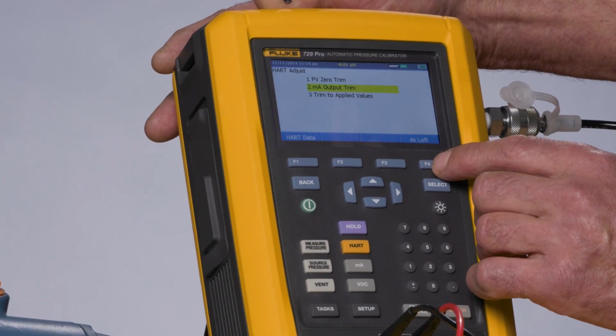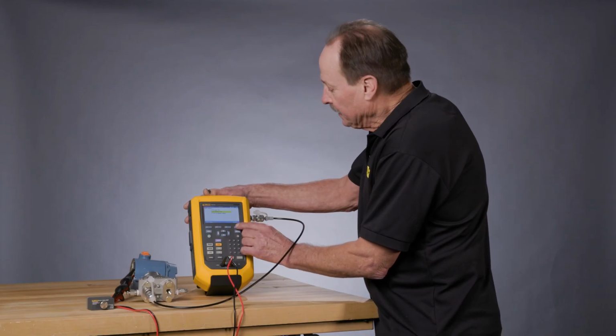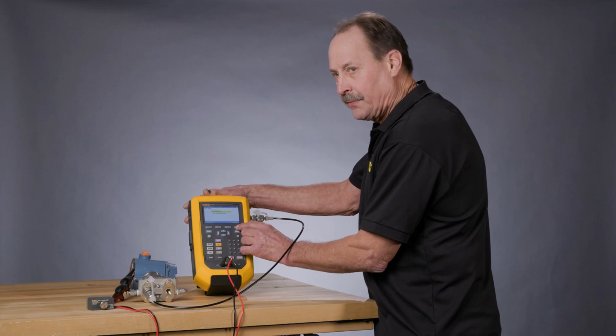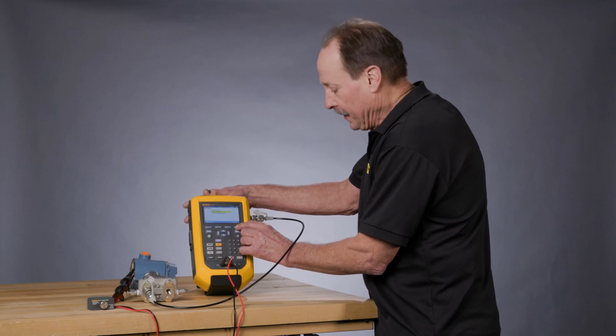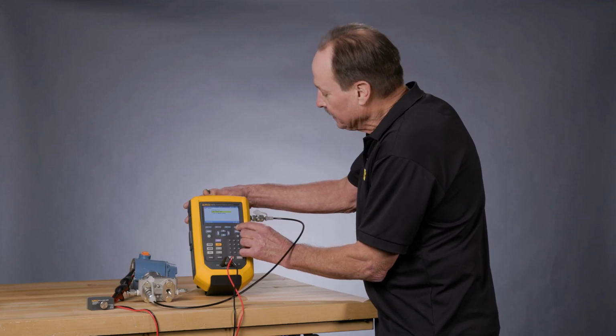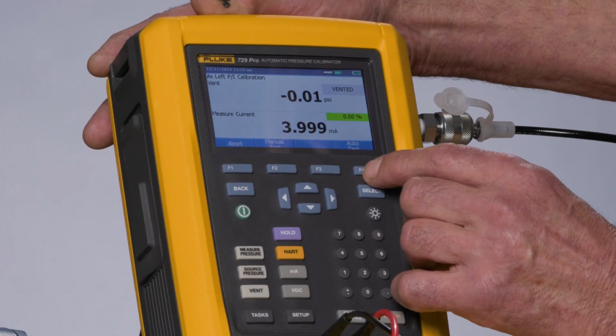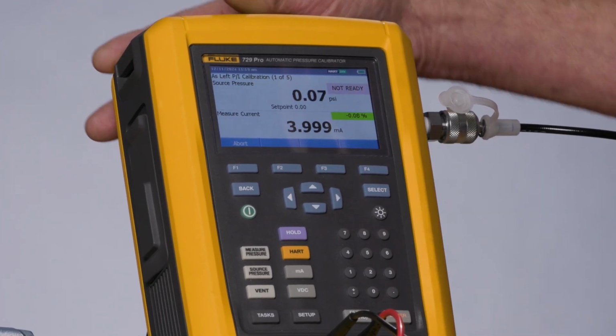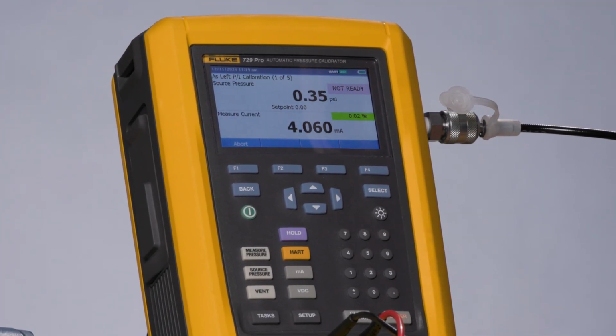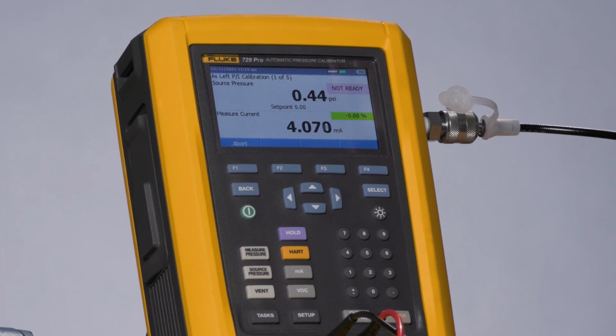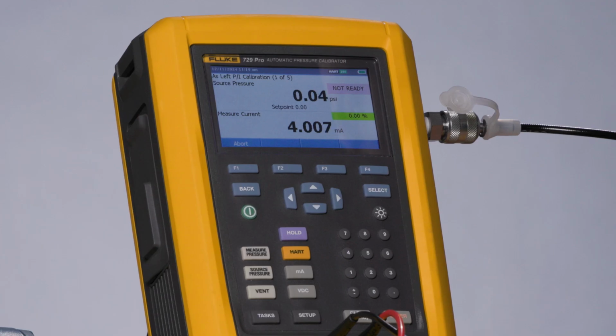Continue. And then I would run the as-left test and confirm that the adjustments that I performed would solve the errors that we saw in the as-found test. So as-left and auto test. And the calibrator will go through and again repeat the test applying 0, 50, and 100 psi and then 50 and 0 psi while measuring for 4, 12, 20, 12, and 4 milliamps and calculating error percent on the measured milliamp signals.